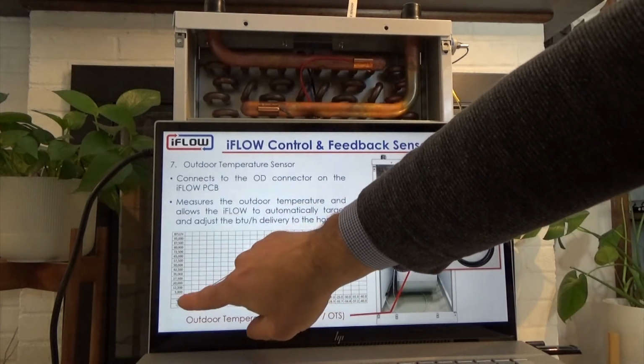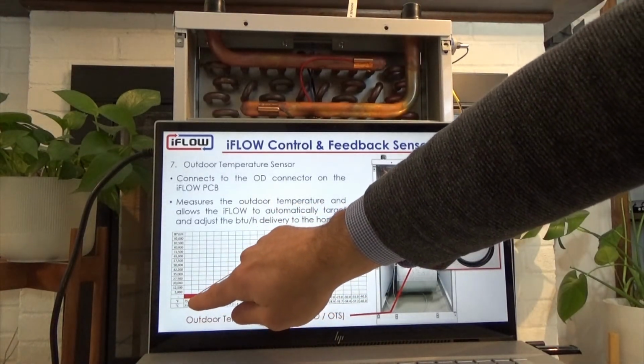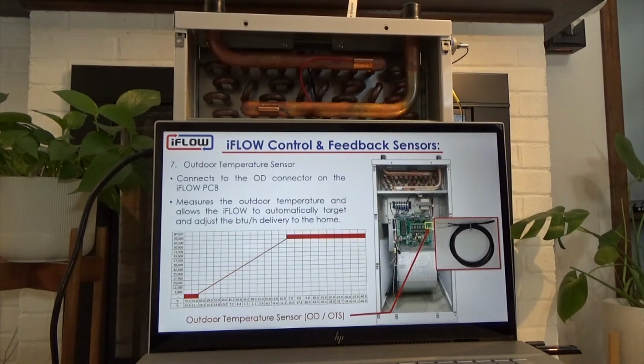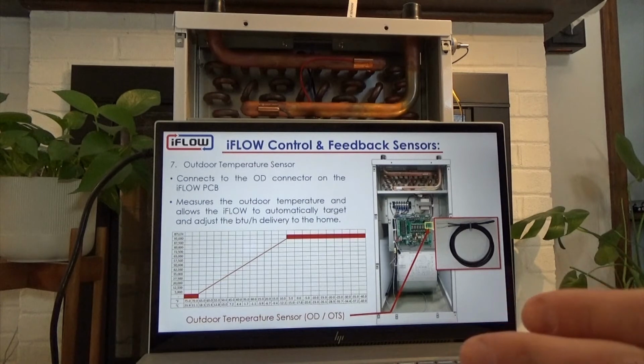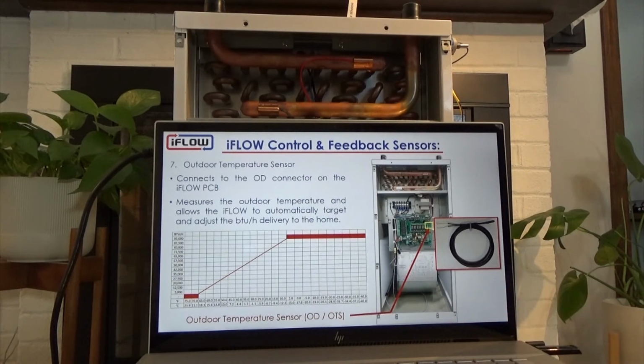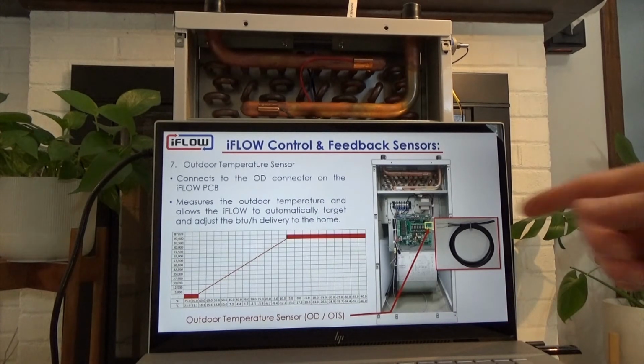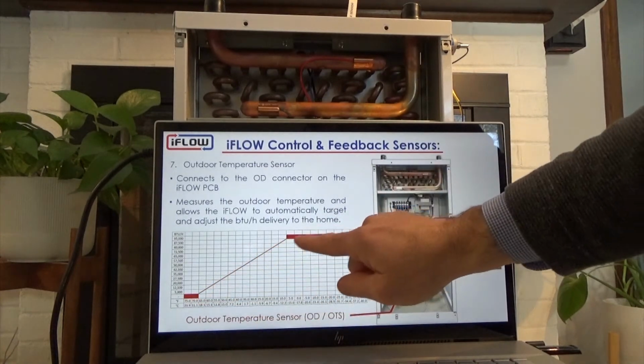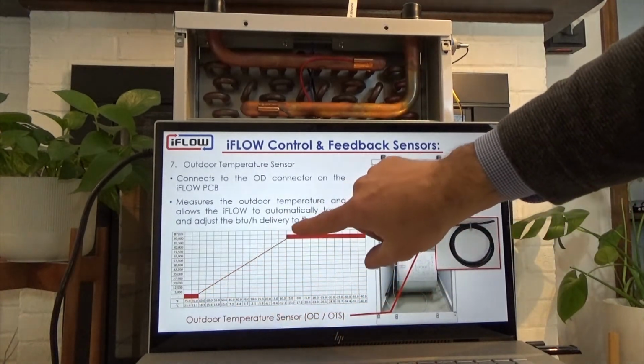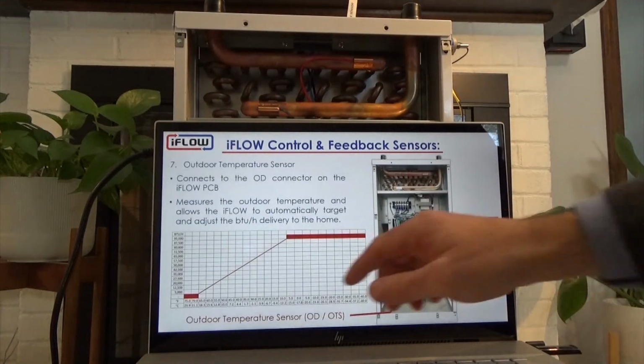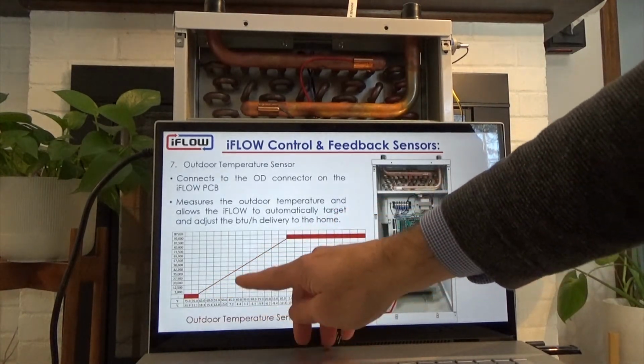On the other side, we've automatically set this point in the slope. Basically, we're saying at 70 degrees and more, you don't need any heating. So below 70, then you will need some heating. And then between those 2 points, we actually get a slope. So we create a slope between those, and that will deliver different temperatures.